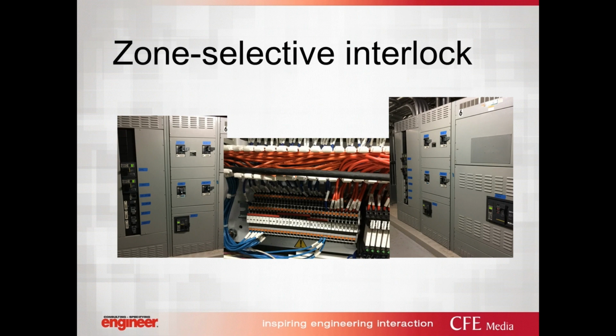Appreciate that, Zia. Zone selective interlock is typically considered a more hands-off way of looking at arc flash mitigation. You don't have issues as you might have with maintenance mode, where somebody could accidentally walk off and leave the system in maintenance mode. However, there are several things that need to be looked at as you're putting the system together. It is highly advanced and engineering intensive, because your entire setup has to be engineered prior to the gear being built. Due to the internal wiring from the factory, it also requires advanced pre-planning, as these cables and this wiring are already built at the factory and sent with the gear.